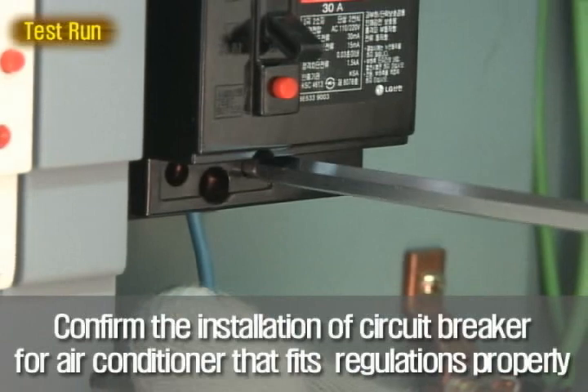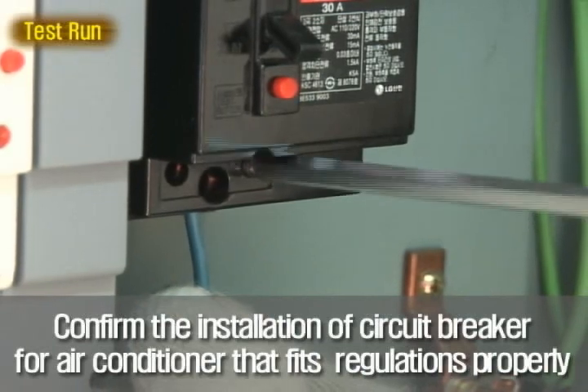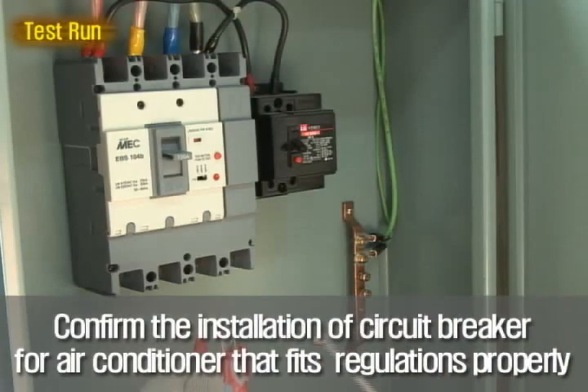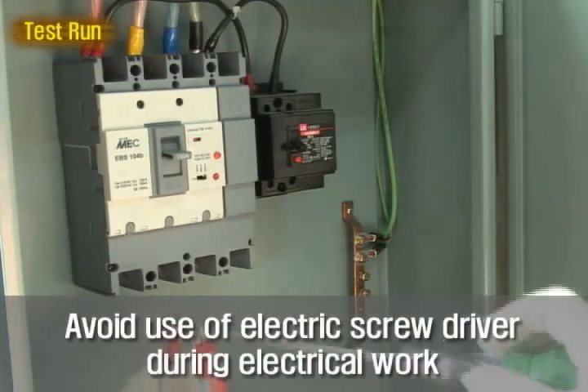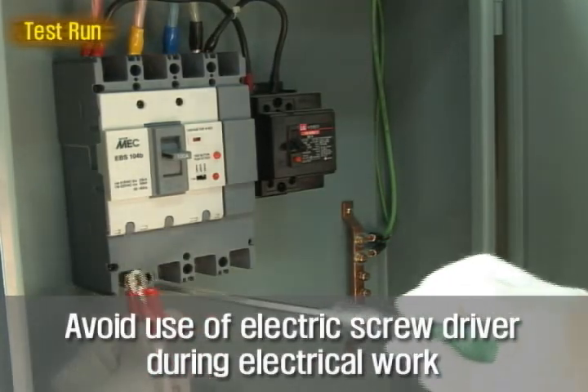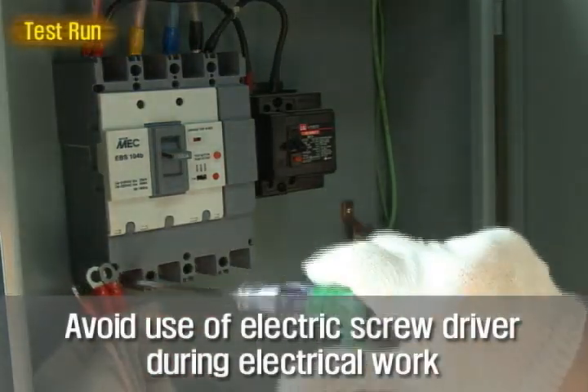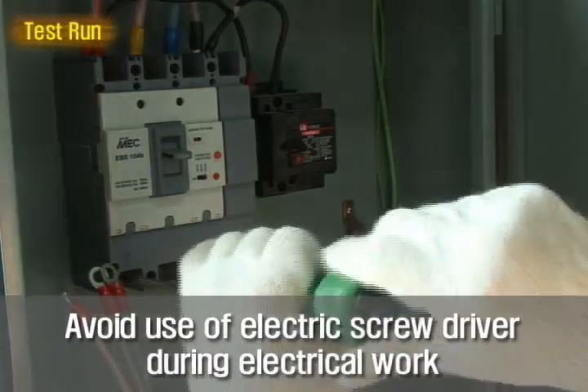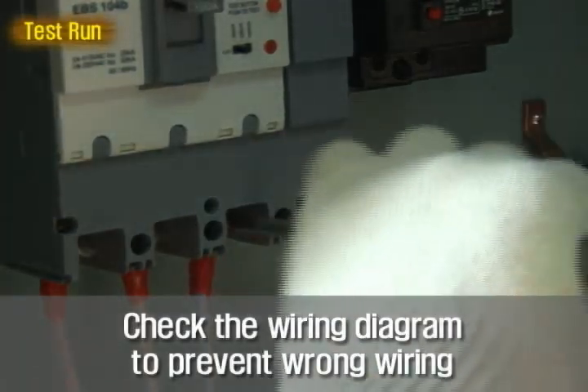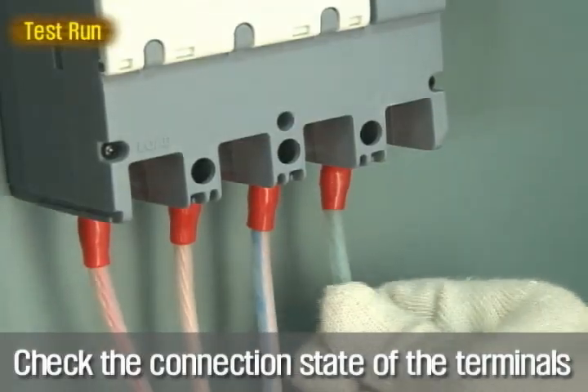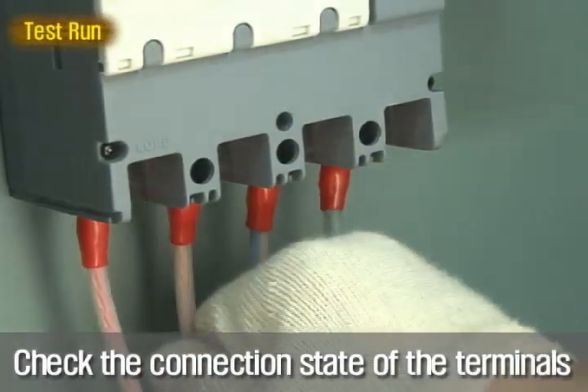Check if the ELB of the air conditioner is proper for the rating and standards, and connect the power lines. In connection, use terminals not to make a connection failure. Check the wiring diagram before connection to prevent wrong wiring, and make sure that the wires will not be loosened with a slight force.